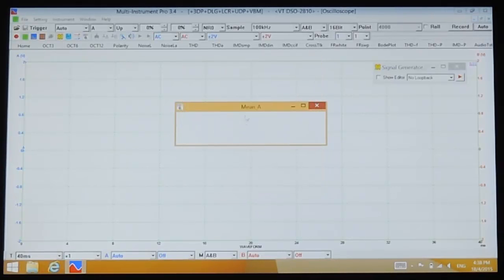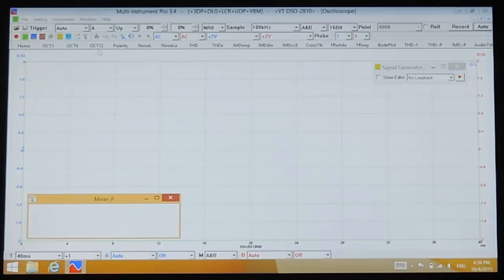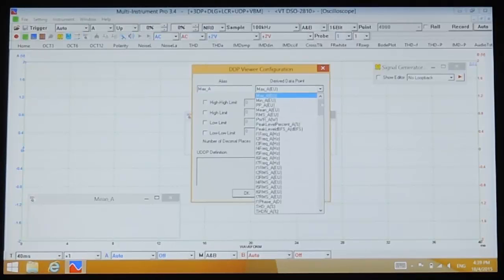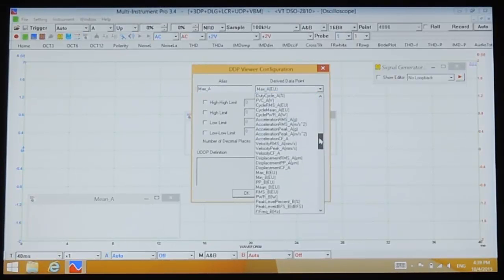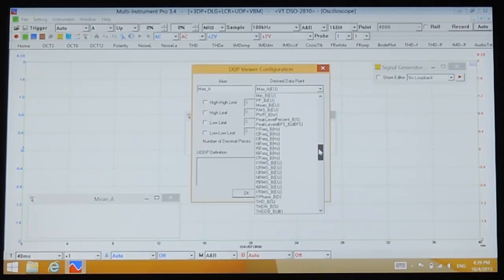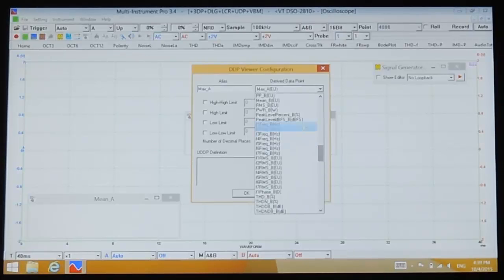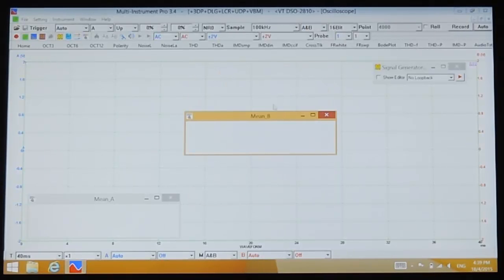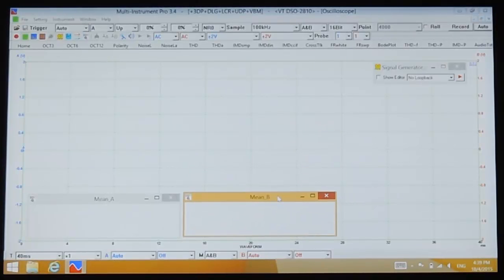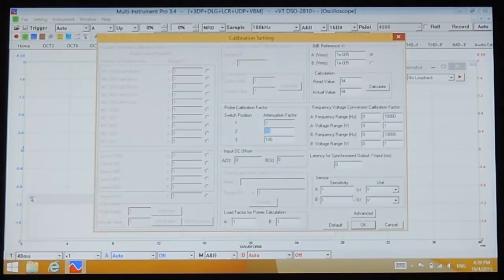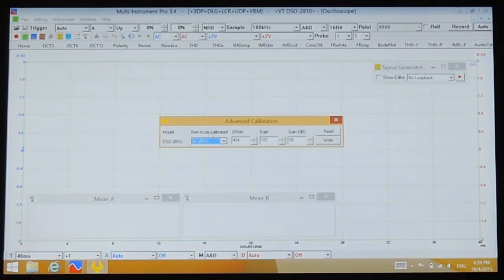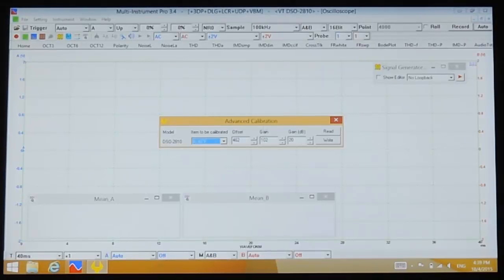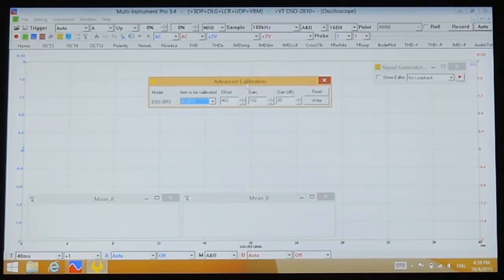Open the DDP viewer and select the mean value for channel A. Open another DDP viewer and select the mean value for channel B. Now go to Setting, Calibration, Advanced to bring out the advanced calibration dialog box. Then select plus minus 2 volts for channel A.